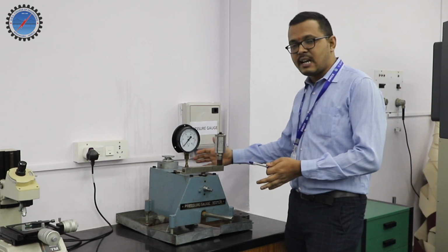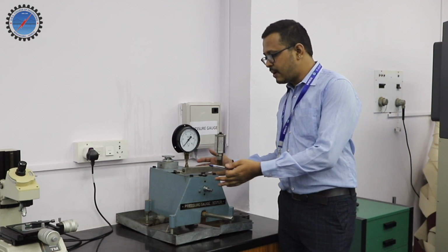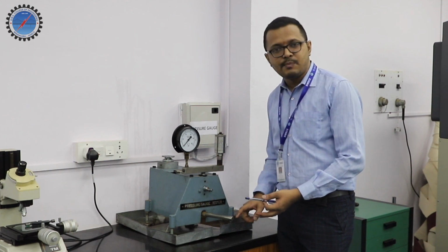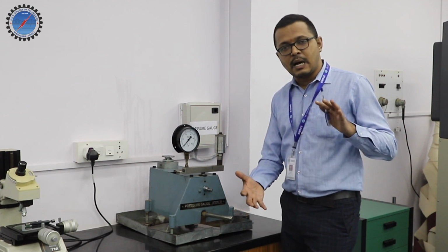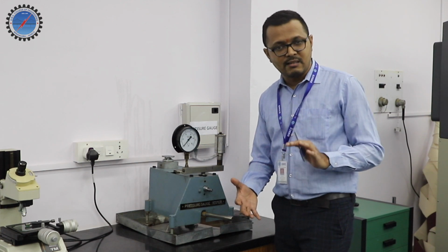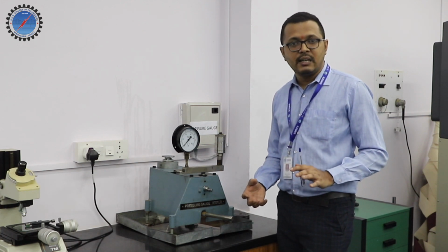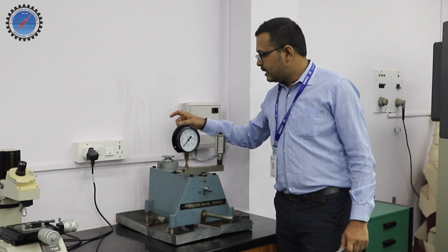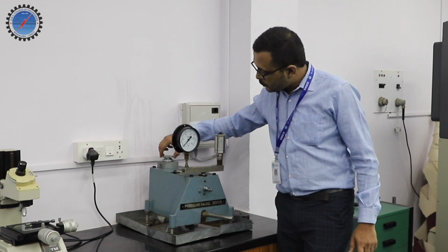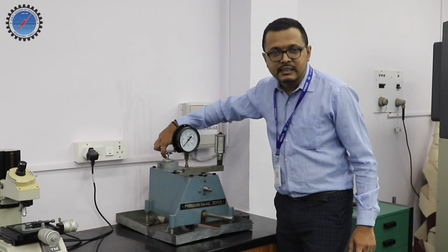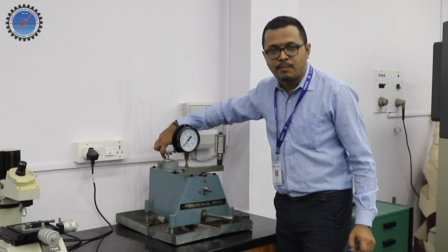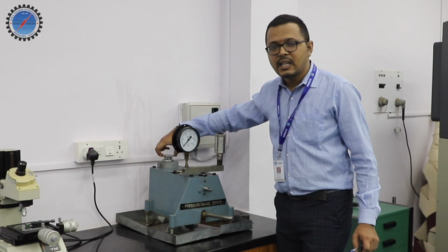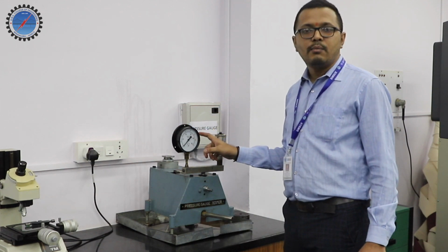I have a piston cylinder arrangement here. I have a cylinder which is filled with hydraulic oil, and a piston arrangement. Whenever the piston compresses the oil in the cylinder, it will build a pressure in the oil that will lift the dead weights. So the load acts on a unit area, which is your plunger, with a small diameter of 5 mm. Force acting on unit area gives you the pressure. That will be directly shown on the Bourdon tube pressure gauge.